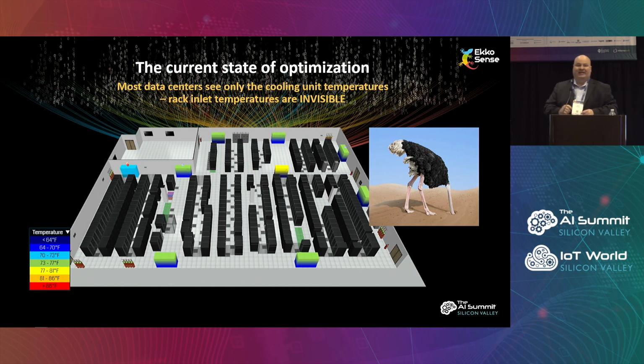In fact, our data shows that less than 5% of all data center operators actually measure what's happening at the rack level at that type of granularity. And if you're not doing that, you have no hope of taking advantage of the advanced technology that AI and machine learning brings to the table. So the operators are trusting that things are going the way they want. They're literally sticking their head in the sand, and they're hoping. Our research shows that 15% of the cabinets in the average data center operate outside of the ASHRAE standards for where they should be for optimal use of the equipment in those racks. That's a high percentage. That's risk they're taking on because of decisions they're making about what they're willing to look at.